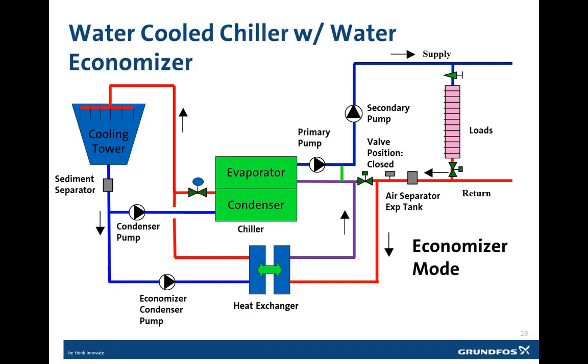In this scenario, the two-way control valve closes, which then directs the water through the heat exchanger, cooling the return water temperature going to the chiller. And this is represented by the purple piping. This ultimately allows the chiller to work less, and therefore it decreases the energy consumption of the system. Now, there are different types of economizer piping configurations, and this configuration is referred to as water pre-cooling. The advantage of this configuration is that it protects the equipment from the open water condenser loop, and for a pump manufacturer, it requires an additional pump.